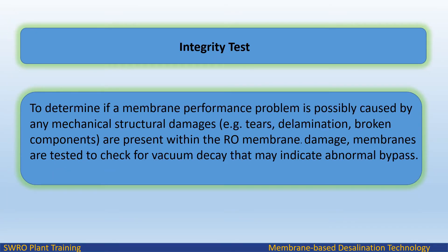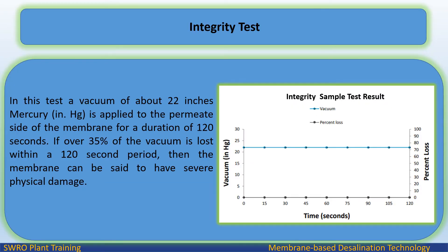Integrity test: This determines if a membrane performance problem is caused by mechanical structural damages such as tears, delamination, or broken components within the RO membrane. Membranes are tested for vacuum decay that may indicate abnormal bypass. A vacuum of about 22 inches mercury (in. Hg) is applied to the permeate side of the membrane for 120 seconds. If over 35% of the vacuum is lost within that 120-second period, the membrane can be said to have severe physical damage.